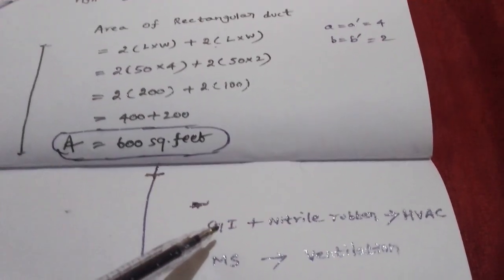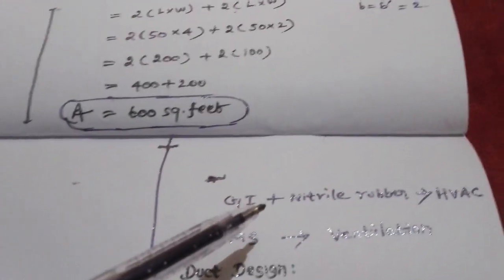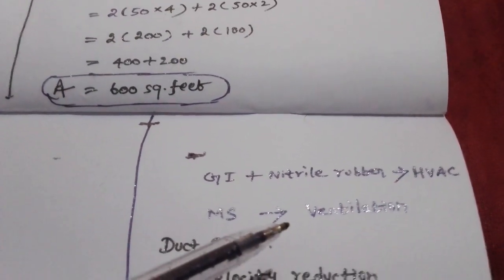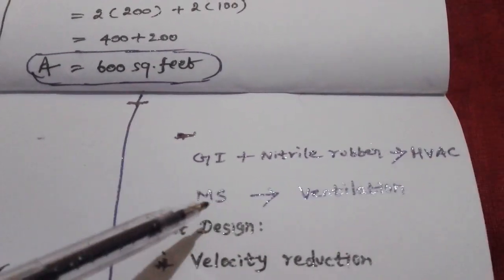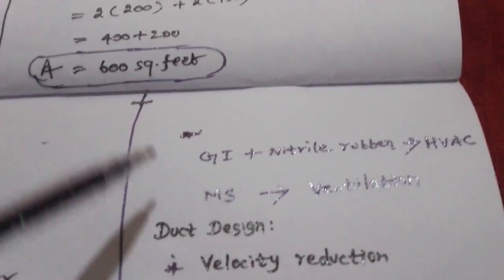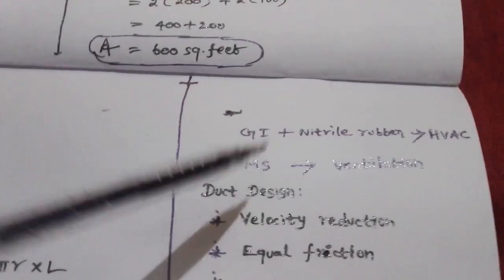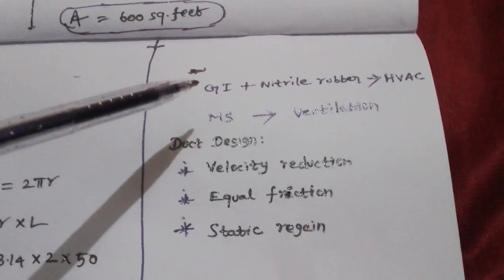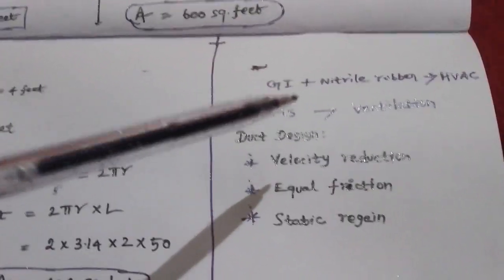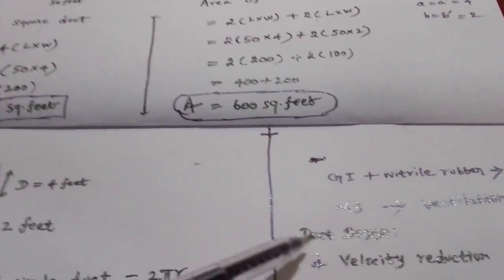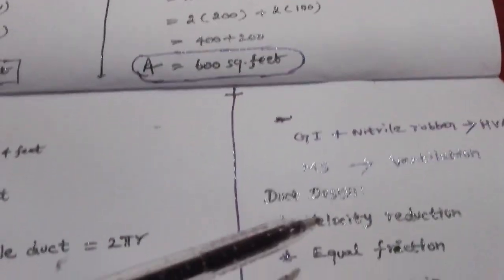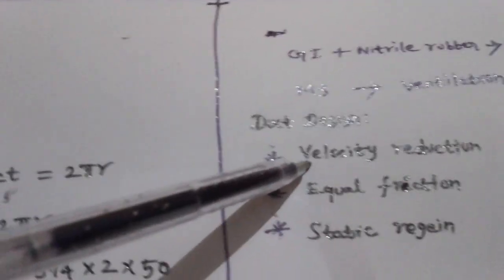The GI duct is made from galvanized iron, which is used in HVAC structures for cool air. It has insulation, and we use nitrile rubber for that. You can use it in ventilation and exhaust systems. You can select the thickness of the duct as needed. For duct design there are three methods: the Velocity Reduction Method, the Equal Friction Method, and the Static Regain Method. The Velocity Reduction Method is the easiest — the velocity is reduced and the duct size is reduced accordingly.